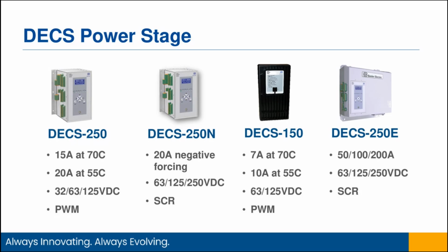We also have a DECS 150, which is a 7 amp power stage, capable of 10 amps at 55C, and it's a pulse width modulated device. And then for our higher excitation applications, we have our DECS 250E, and we're able to produce that product at multiple levels of excitation current, anywhere from 50 amps to 200 amps. And that one uses an SCR-based power stage.